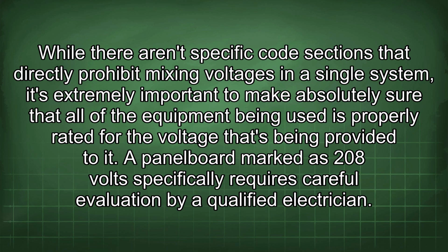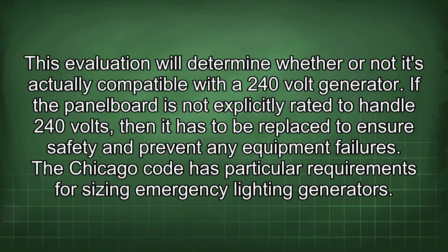A panel board marked as 208 volts specifically requires careful evaluation by a qualified electrician. This evaluation will determine whether or not it's actually compatible with a 240 volt generator. If the panel board is not explicitly rated to handle 240 volts, then it has to be replaced to ensure safety and prevent any equipment failures.